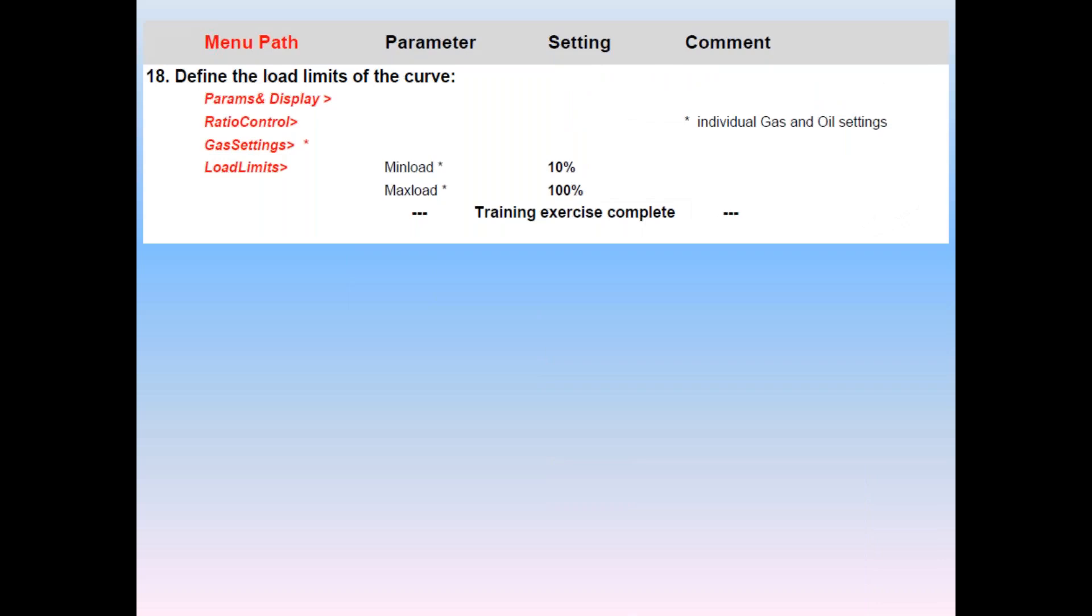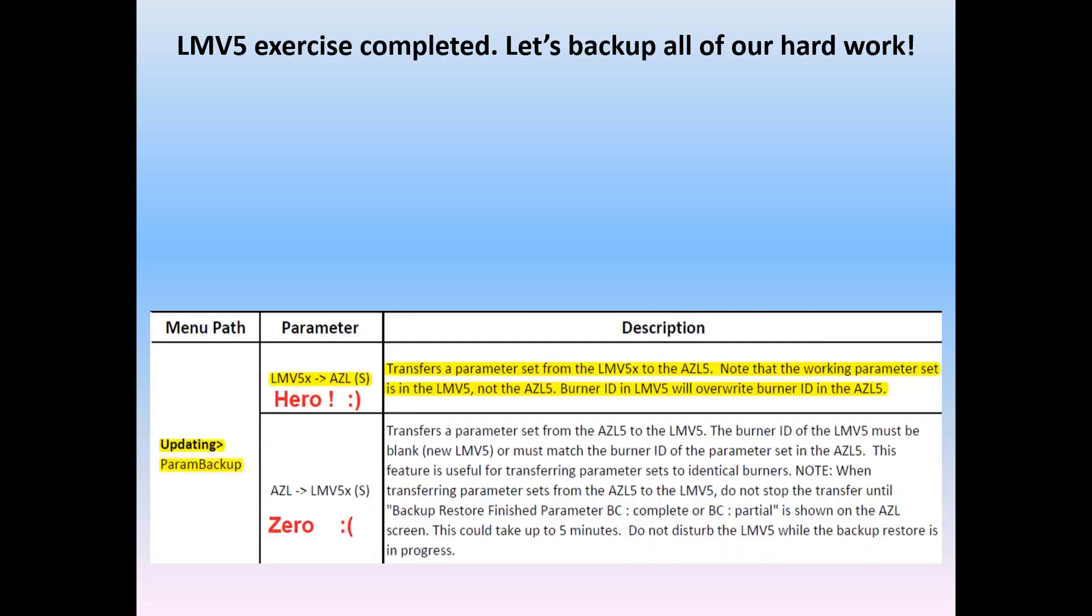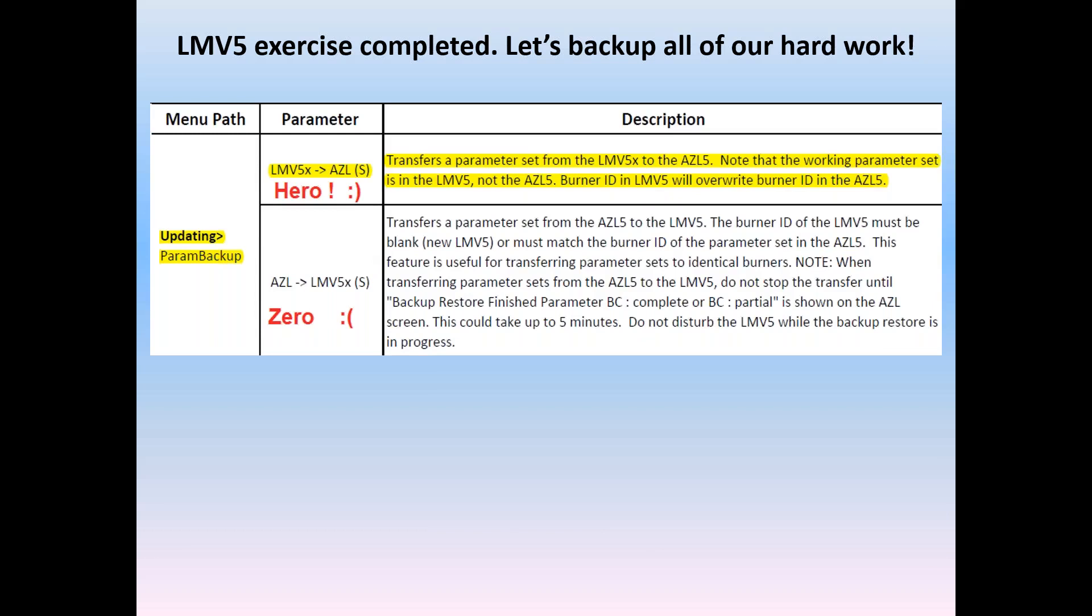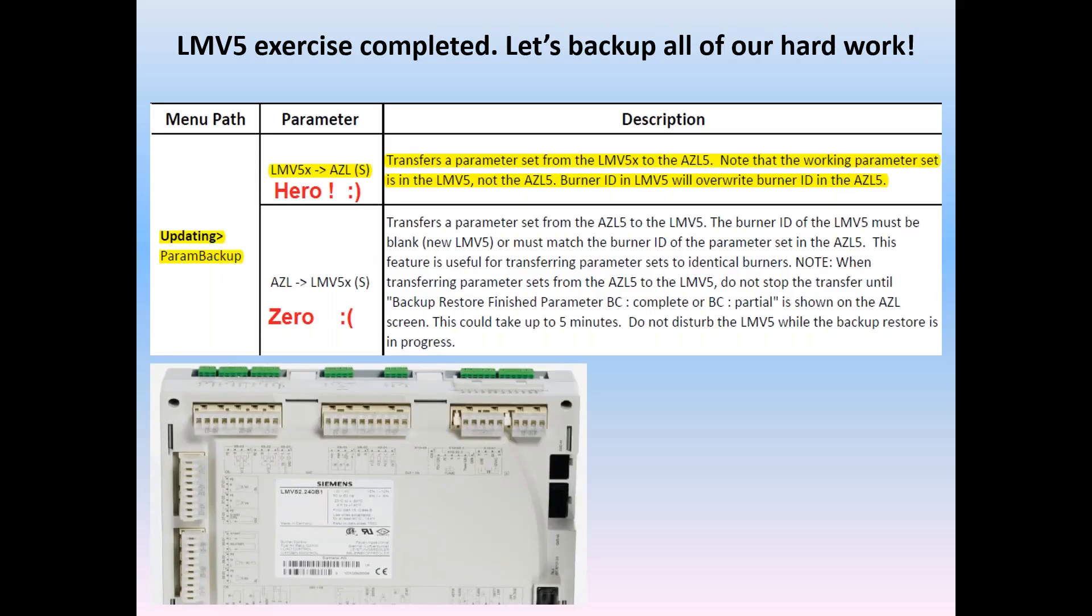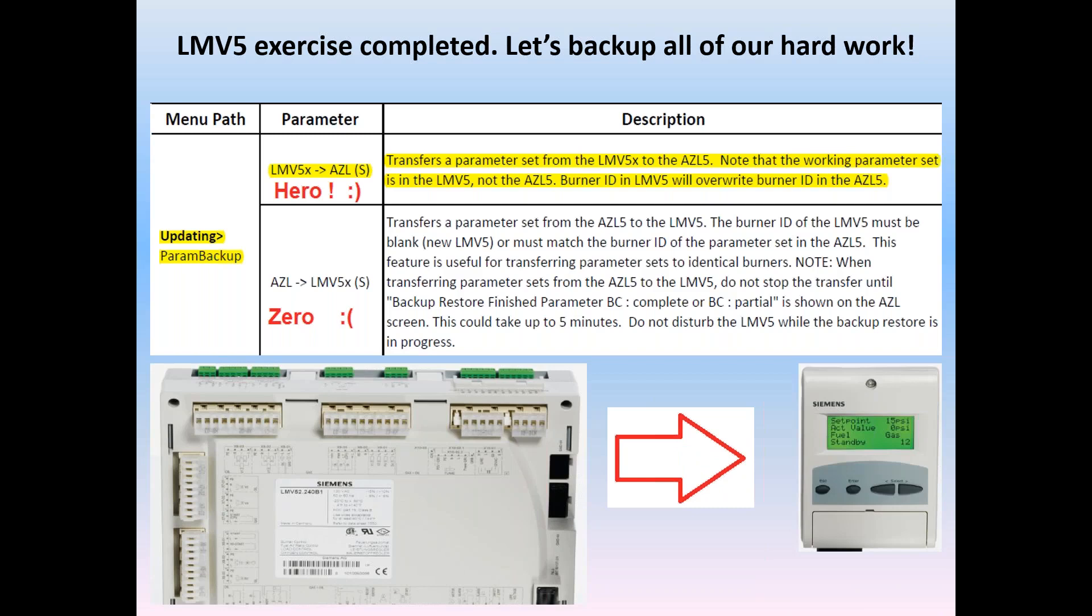You continue on with this until you get to the top of your curve pretty much 100 percent firing rate with as many points as you would like to put in there with as little as no points firing ignition position all the way up to a maximum number of 15 points and you can add and delete points at your leisure. Finally, number 18, we can define how much of that great curve that we built we want the LMV-5 to use on this job site by setting the min and the max values. Important, really important. All that great work that you did setting up the LMV-5 and now we should make a backup. I want to stress that even though we had that AZL keyboard in our hands and we saw the AZL display all the values that we entered, all, all of what we had done was on the LMV-5 itself. Truthfully, we could put any AZL on our LMV-5 and the unit and the program would be the same. The LMV is the flame safeguard. The AZL is the HMI, the human machine interface. Okay, let's do a backup. Let's be a hero. Let's not be a zero. We're going to take everything that we did on the LMV-5 and we're going to take it to the AZL. So we're going to pick LMV-5 to AZL and perform the backup.